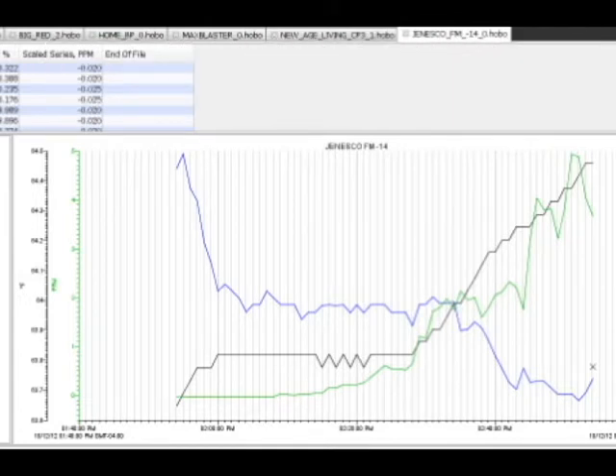Well folks, you're looking at the data record from our data logger in the ozone testing chamber here at our shop at Prozone. You're looking at the data from the test we did on the Jenesco FM14. This test started at right around 1:47 p.m. and ran till around 2:47 to 2:50 p.m. You can see the green line indicates the maximum ozone levels achieved in a 15 by 15 room.